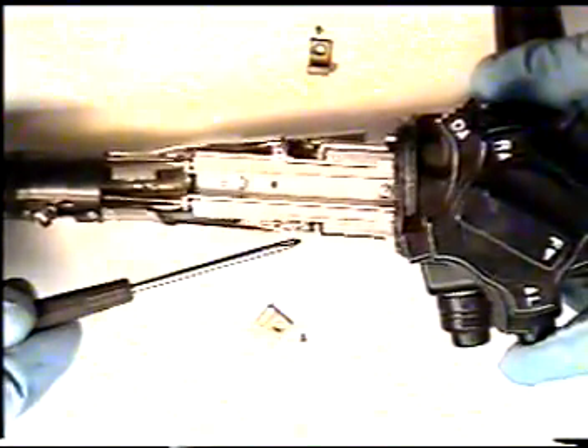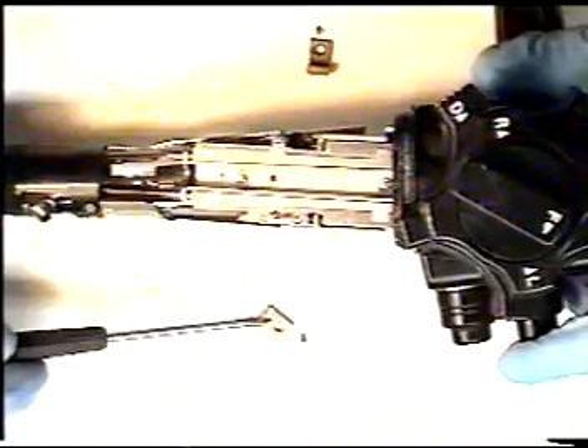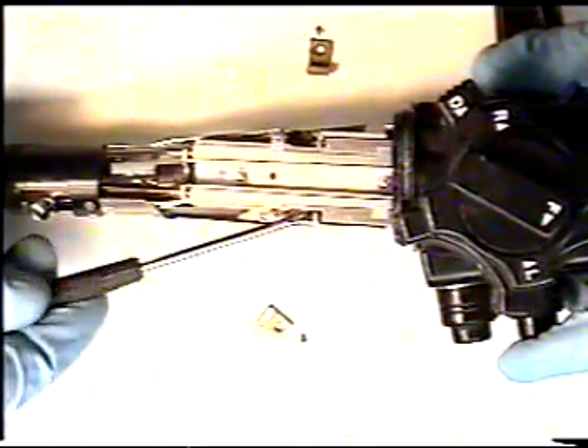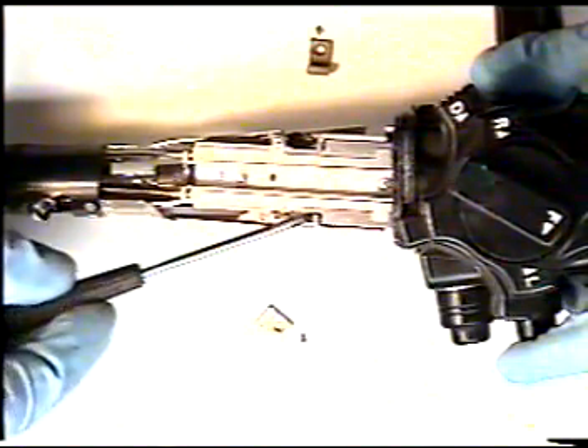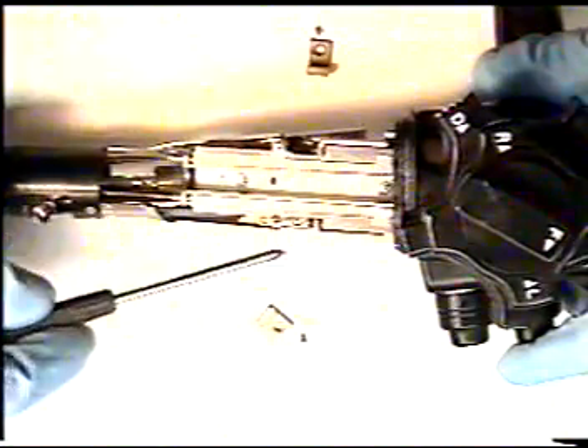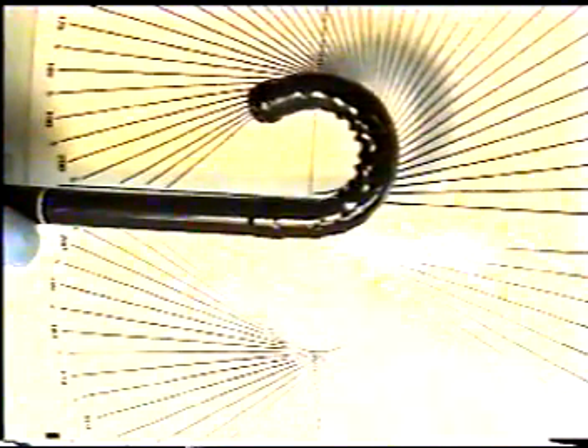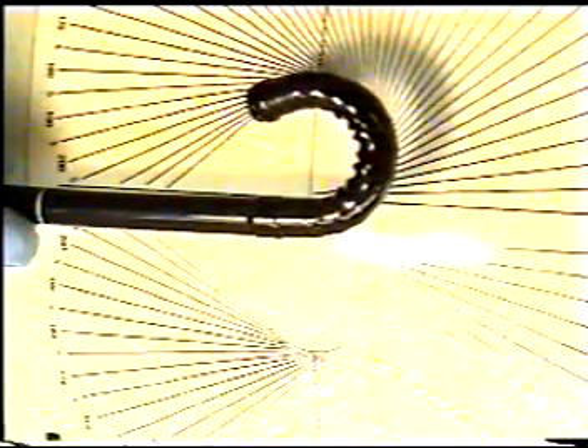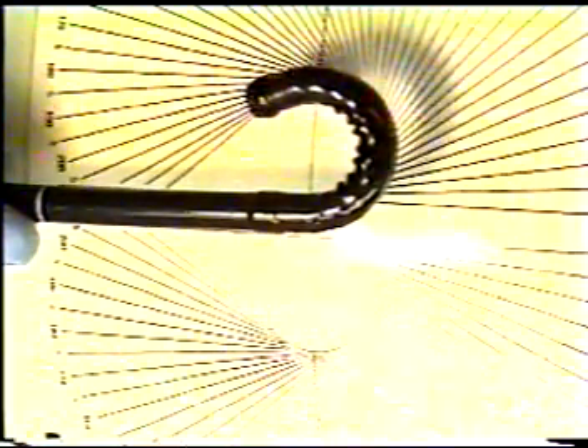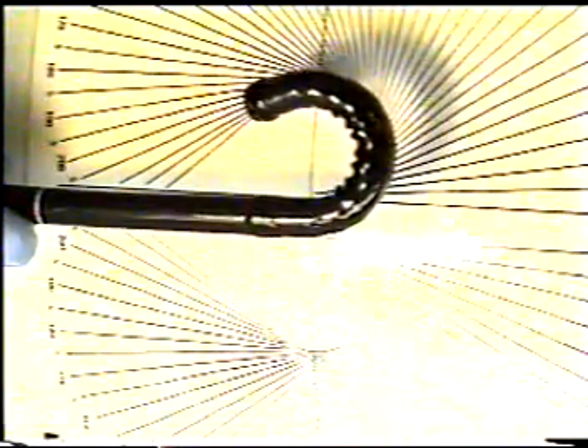The angulation cable adjustments are the 4 screws which we have just accessed by removing the covers. They can be adjusted either anti-clockwise or clockwise. Using your angulation control chart included with the video, we will now have to adjust the endoscope for proper manufacturer specification angulation. To adjust for proper angulation, consult Olympus operating manuals for proper angulation. In this case, GIF XQ20 Olympus gastroscope will need an angulation adjustment of 210 up angulation.